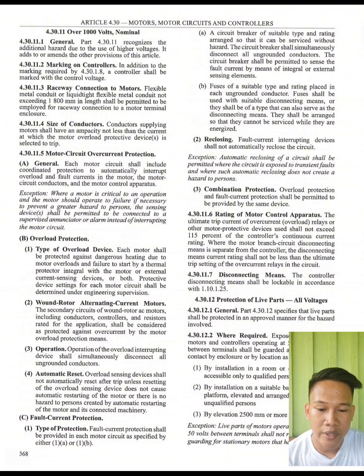So next is 4.30.11.3 Raceway connections to motors. Flexible metal conduit or liquid tight flexible metal conduit not exceeding 1,800 mm in length shall be permitted to be employed for raceway connections to a motor terminal enclosure. Next is 4.30.11.4 Size of conductors. Conductors supplying motor shall have an ampacity not less than the current at which the motor overload protective device is selected to trip.